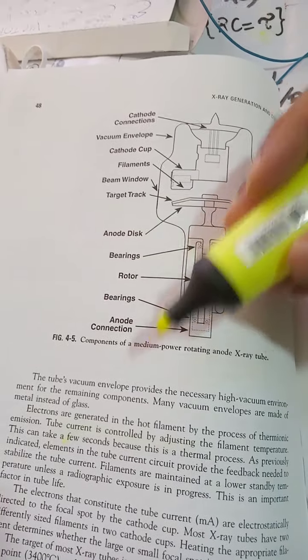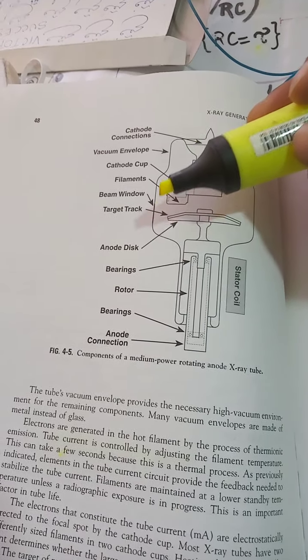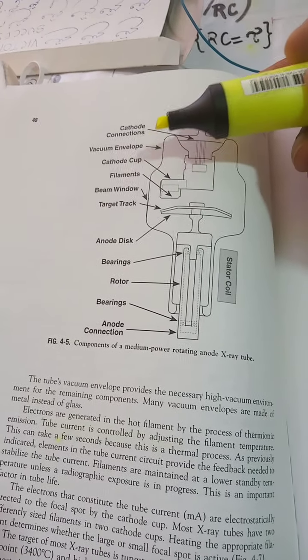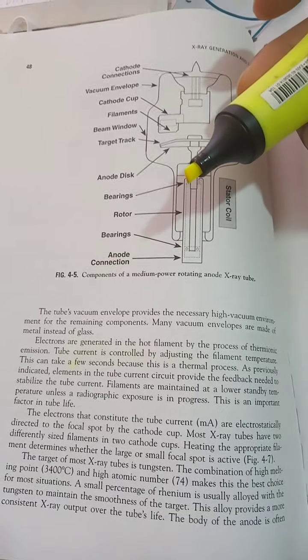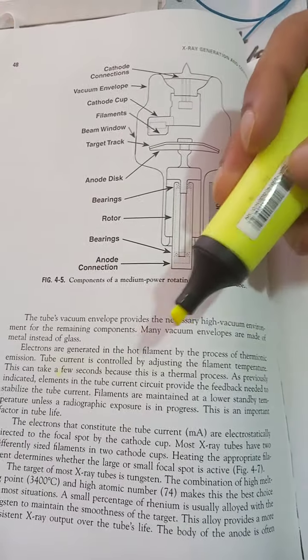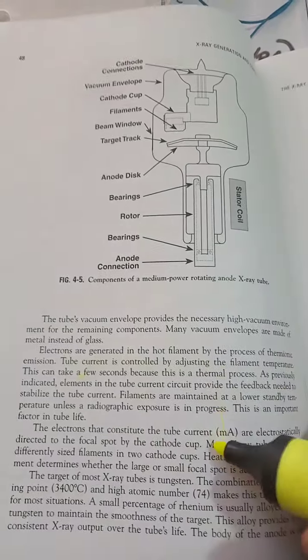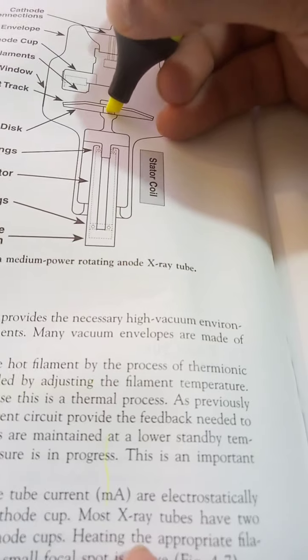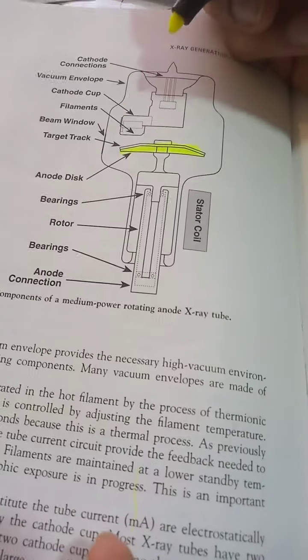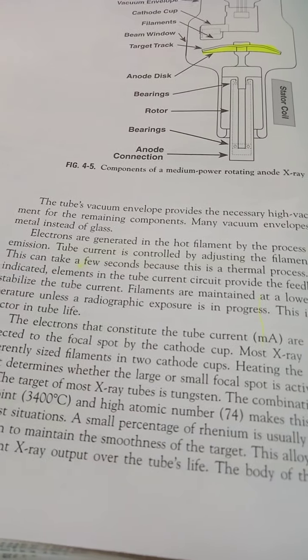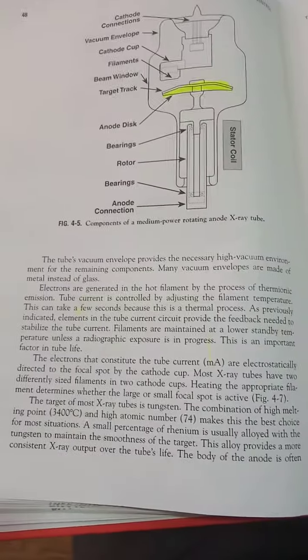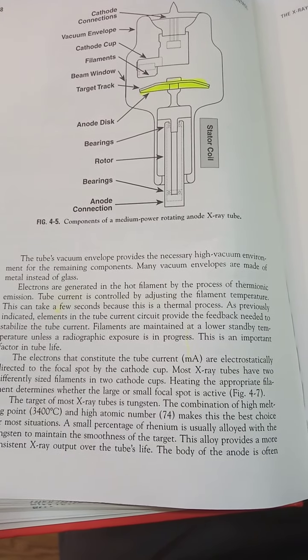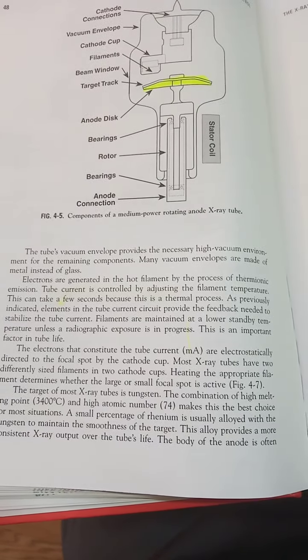The bearings, rotor bearings, anode, the rotating anode, the target track, beam window, filaments, cathode cup, the vacuum envelope, cathode connections. So the tube's vacuum envelope provides the necessary high vacuum environment for the remaining components. Most vacuum envelopes are made of metal instead of glass.